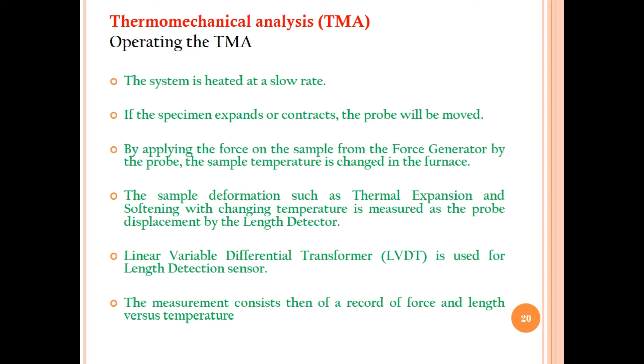How do we prepare the sample for TMA? First of all, we look into the sample preparation. If we have bulk samples, parallel faces are needed for expansion, and reasonably flat for penetration. That we have already discussed. Different types of probes are used for sample analysis, depending upon which kind of sample is under observation in TMA. Films and fibers are cut and mounted using fixtures. Use razors to avoid tears and cracks, which means if we want to analyze films or fibers by the TMA technique, they should be flat and free from tears and cracks. Because with tears and cracks, it may disturb the temperature measurement and expansion measurement when we apply a load in TMA.